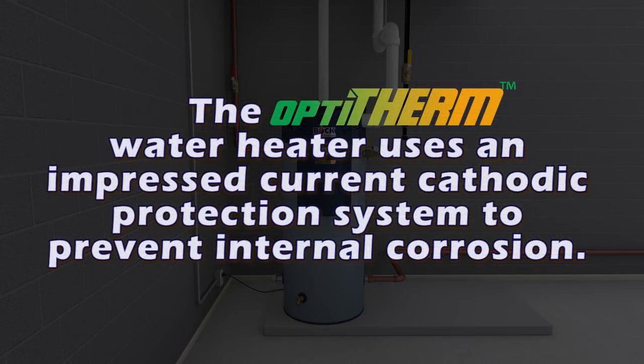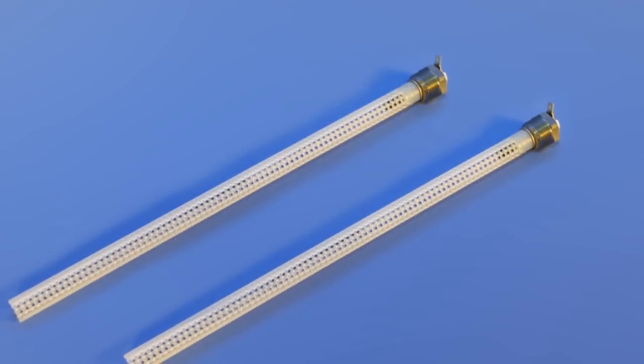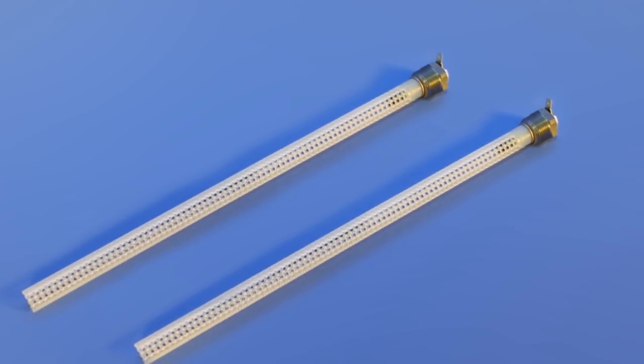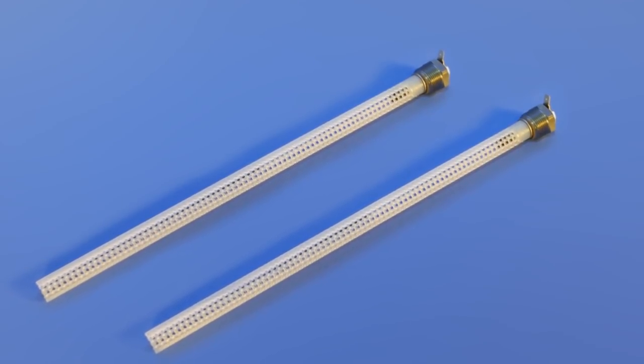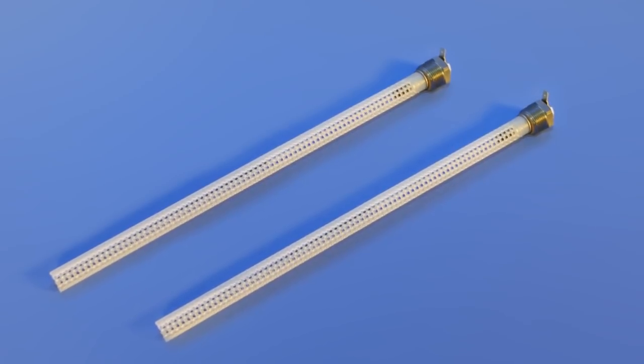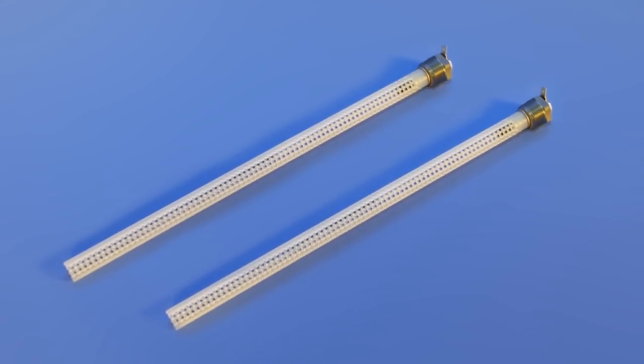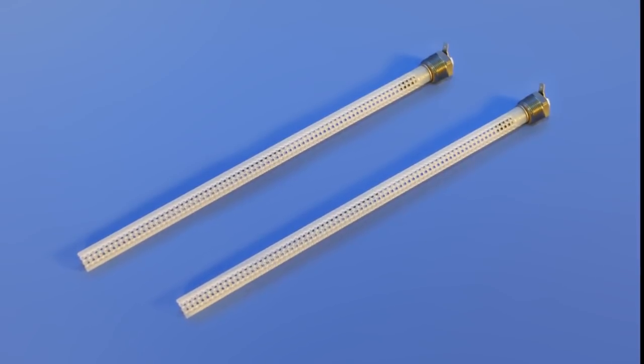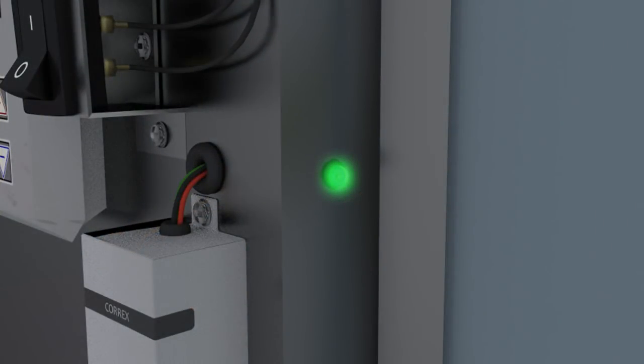To prevent internal corrosion, the optiTHERM water heater uses an impressed current cathodic protection system instead of the traditional sacrificial anode rod. This system uses 2 powered electrodes and regulates the protective current based on actual conditions inside the tank. These electrodes are not consumed over time and do not need to be visually inspected or replaced. An LED shows the current status of the system. A green LED indicates proper operation. The LED flashes red when the system is not functioning correctly.